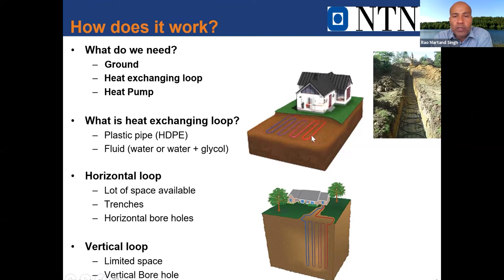The type of loop - horizontal or vertical - depends on the space we have. If we have a lot of space, we go for horizontal loops. So if you live in the countryside, or have a university with a sports field, that space can be utilized to put the loops. But if we live in the center of a city, we don't have much space, so we need to go vertically down. The vertical option is more expensive because we need to drill so deep - in this case we go up to 100 meters deep, which is why it is more expensive.